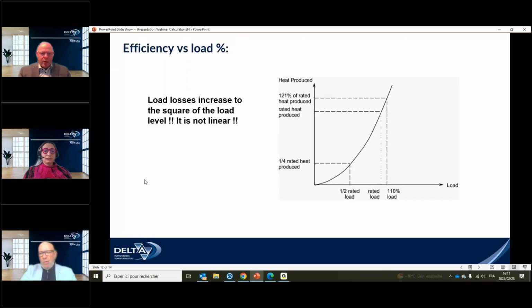One thing to remember about transformers, and that's a very important point, you have two types of losses in a transformer. You have no load losses, the losses of the core itself, and you have load losses, the losses of the windings. As soon as you energize a transformer, the core magnetizes, and you're stuck with those no load losses. They are present even if you have nothing connected to your secondary. So that's one thing you have to look at, and one way we can make a transformer more efficient is by lowering those no load losses. And then we have load losses, the losses in the windings themselves.